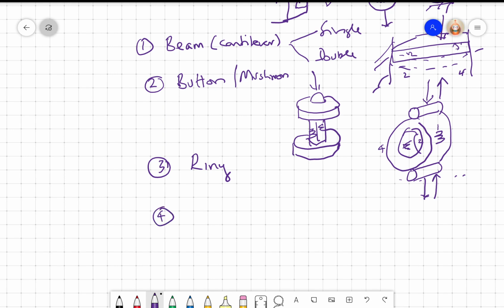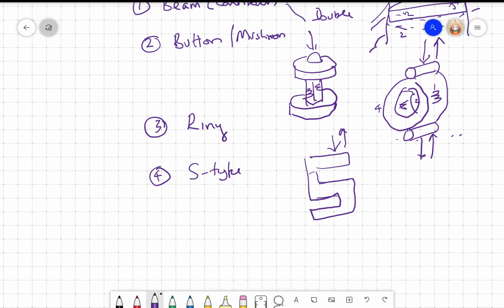The last is the S type load cell. So what you do is make this structure and apply a force here. This again you can put compressive force or tensile force. It will work nicely. This is also very popular because it has a very good sensitivity. So if you want to measure micrograms, you normally use an S-type load cell.